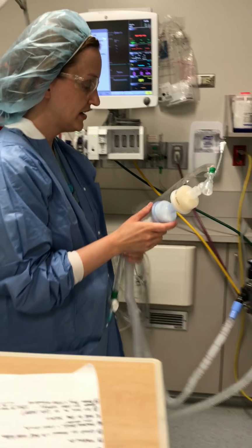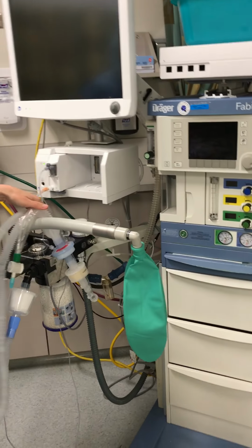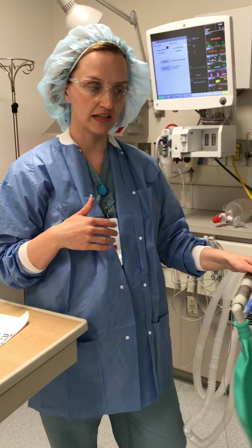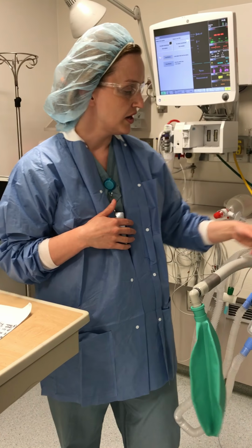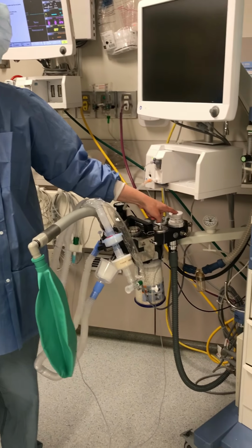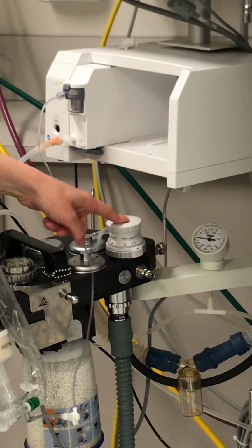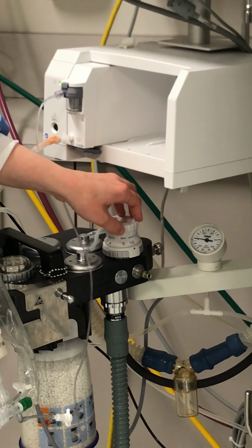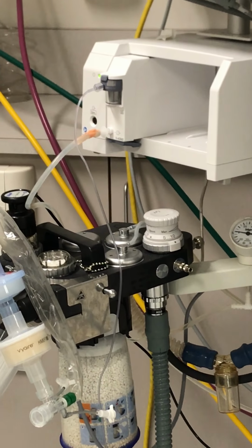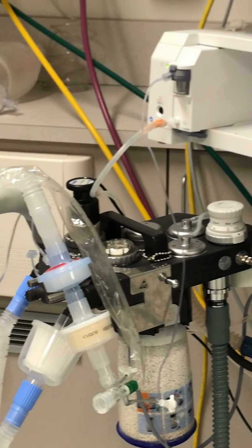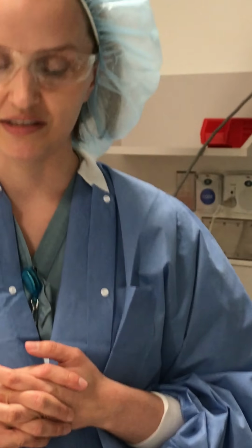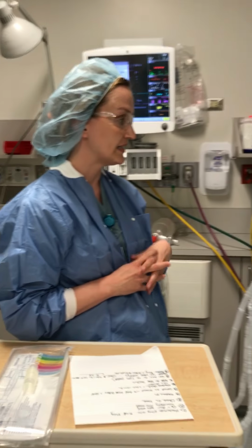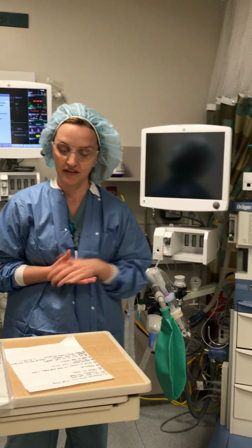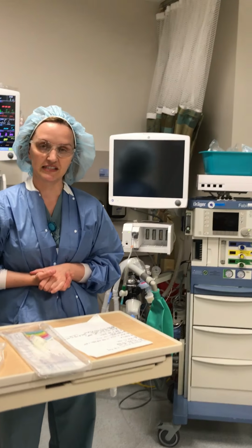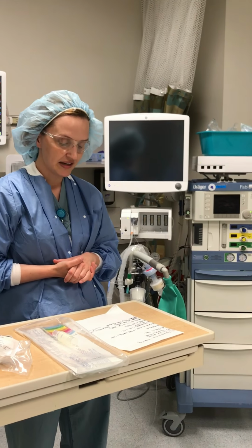Other things to check, which are part of our standard machine check flow sheets that you'll see in a separate video: you want the APL valve set to what you're expecting the patient's PEEP to be. So I suggest a minimum of 10, so that if the vent fails, you'll be at least delivering 10 centimeters of water pressure to the patient until you're able to intervene. You'll then want to set your ventilator settings for what you're expecting, and hopefully you've had time to talk to the ICU team about this.